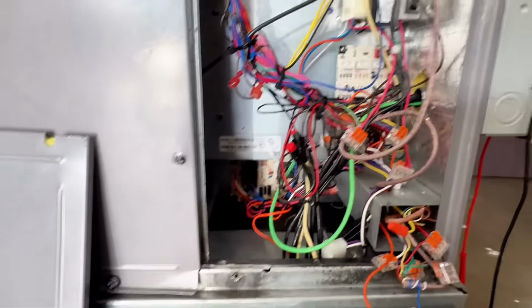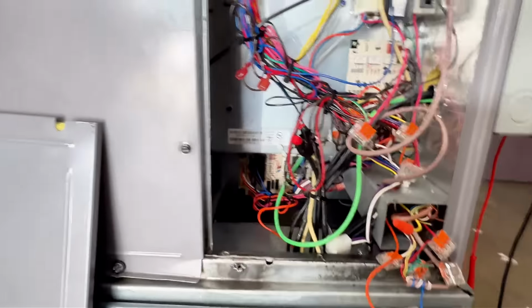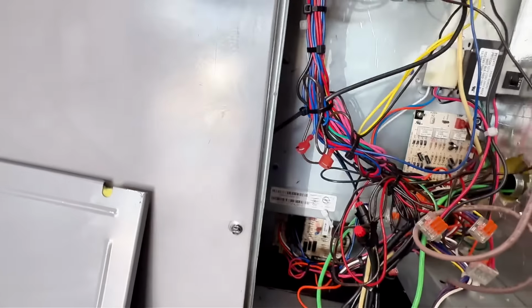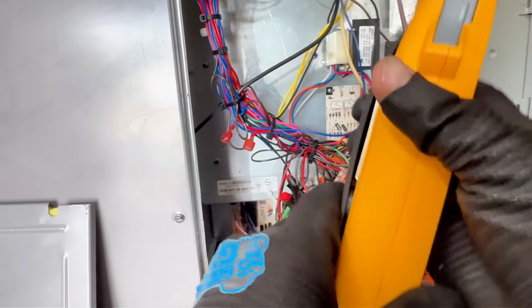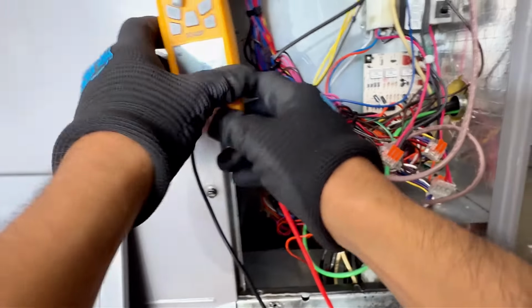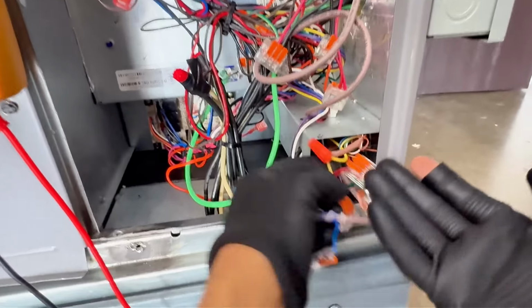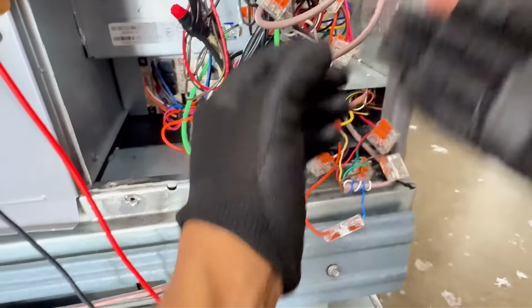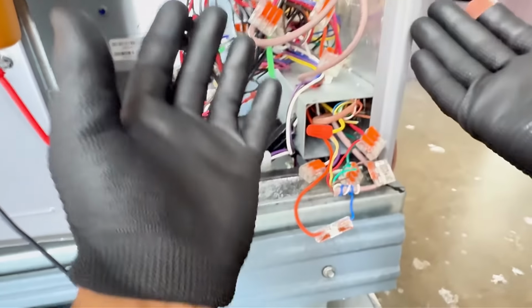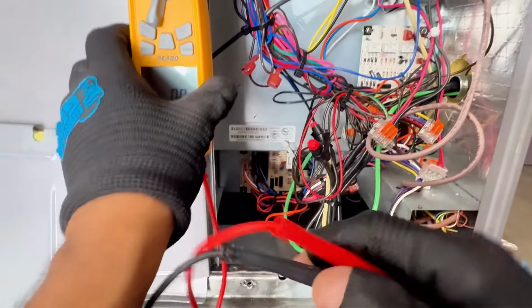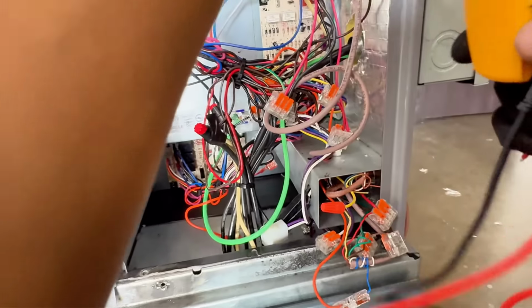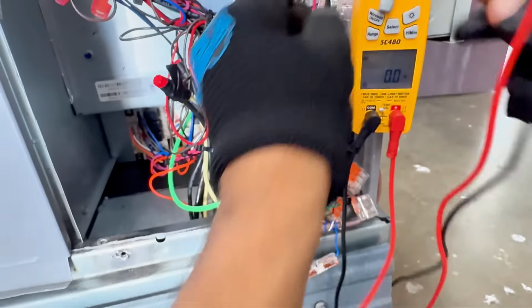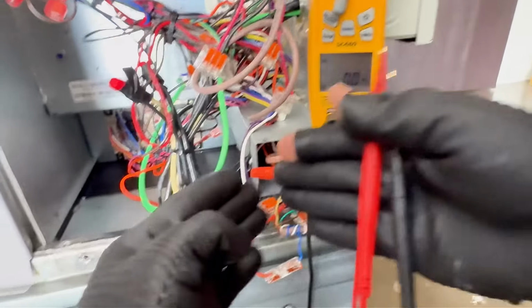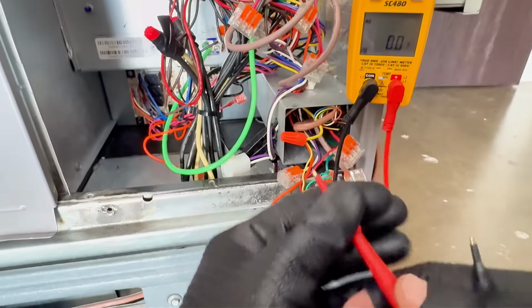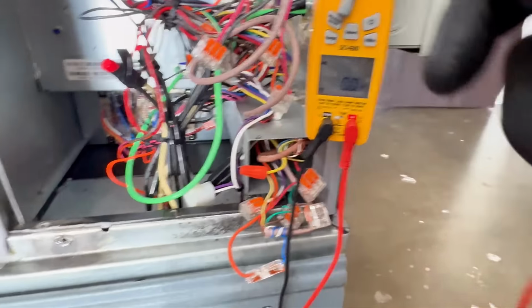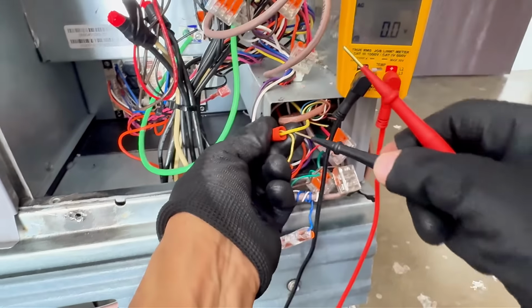All right. So this is where I would confirm that just because your thermostat is calling for cooling, it could mean that something else is going on. What I mean by that is that my thermostat wires come right here. There could be an issue going on with the thermostat wires, or my thermostat head might be bad. So a lot of the times what I like to do is put it on VAC, okay? And I just confirm with the wires that are wire nutted to the unit if I have 24 volts coming in here, because your thermostat could be bad. But I think it's good because I heard something click.